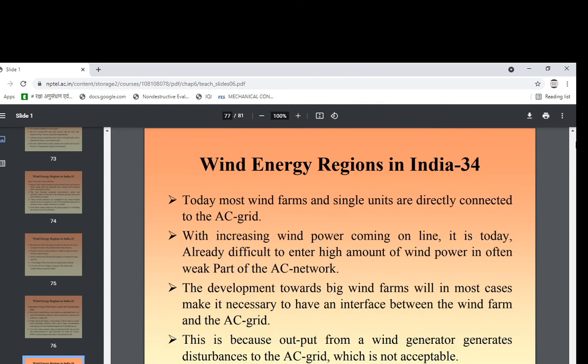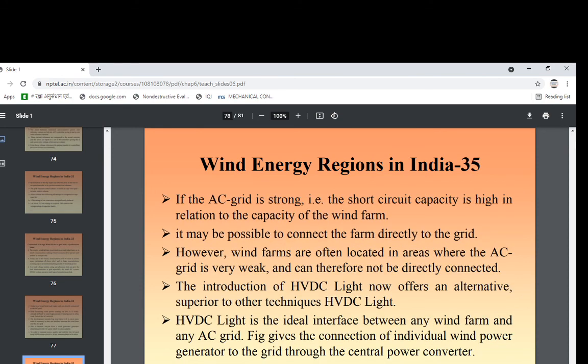Today, most wind farms and single units are directly connected to the AC grid. With increasing wind power coming online, it is today already difficult to feed high amounts of wind power into often weak parts of the AC network. If the AC grid is strong, the short circuit capacity is high in relation to the capacity of the wind farm, and it may be possible to connect the farm directly to the grid. However, wind farms are often located in areas where the AC grid is very weak and therefore cannot be directly connected. The introduction of HVDC Light is now an alternative and superior technique.